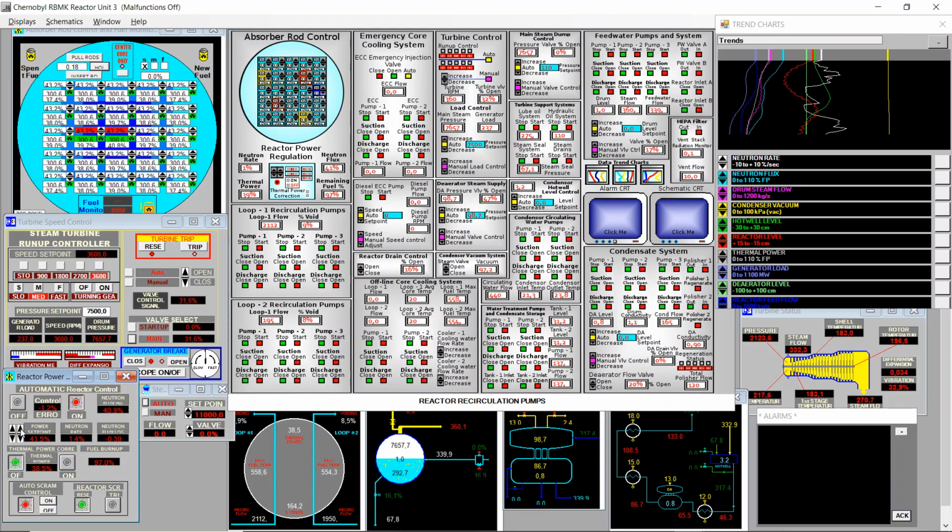And now it's the moment to take care of the turbine, because when we start increasing power very fast, we will hit the rotor much faster than the shell. We see here the rotor at 204 degrees, the shell at 187. This creates differential expansion. We have a differential expansion of 0.059. I guess this is in meters, so this is 62 millimeters, probably, I don't know.